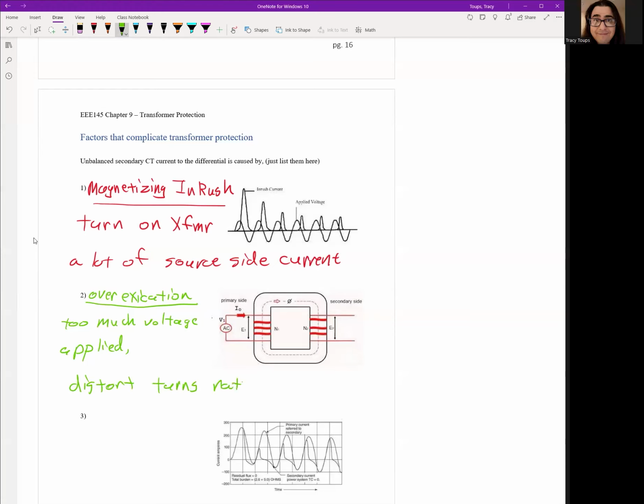Right. Once a transformer goes into saturation, or sorry, overexcitation, which turns into saturation, your turns ratio is not constant anymore. So for example, if we put too much voltage and we have overexcitation in the transformer and we increase or decrease a current, the secondary side will not respond in a linear fashion. So you might see some funky things happening. Again, because we're distorting the turns ratio, the differential protection does not like when the turns ratio changes, right? So that's another big issue we have to deal with.